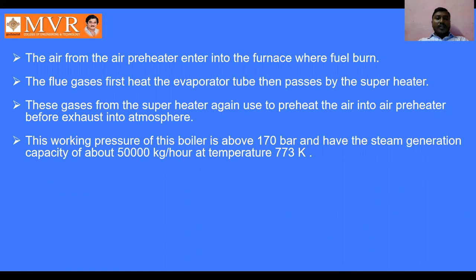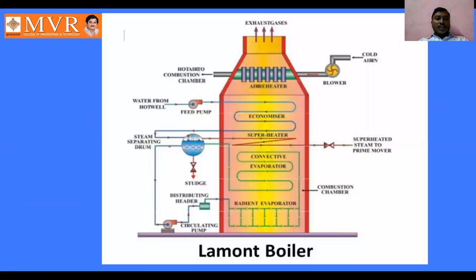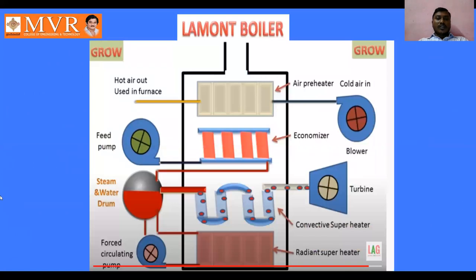The air from the air preheater enters into the furnace where fuel burns. The flue gases first heat the evaporator tube and then pass by the superheater. These gases from the superheater are again used to preheat the air in the air preheater before exhausting. This is the working principle of a Lamont boiler, which we can observe here: the cold air is going to enter the air preheater.